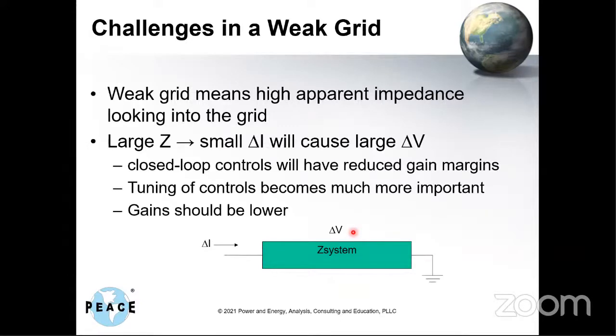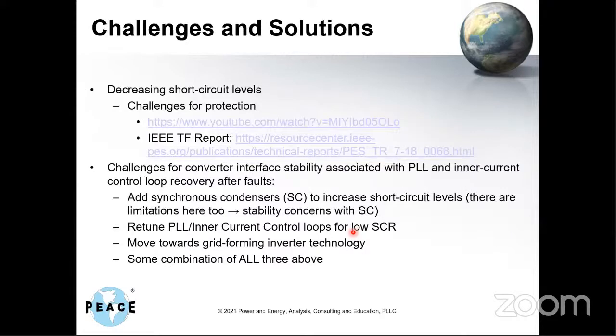And so it becomes more and more difficult to control voltage, and therefore you lose gain margin on your closed loop controls. And similarly, you lose gain margin because frequency changes much faster. You'll lose gain margin on things like your PLL trying to lock on to the frequency after an event. So tuning of controls becomes much more important, and you may need lower gains to make everything work. And at some point, you may need to have something else to help you, and that's where some of these potential solutions come in. You may need to increase short circuit strength.